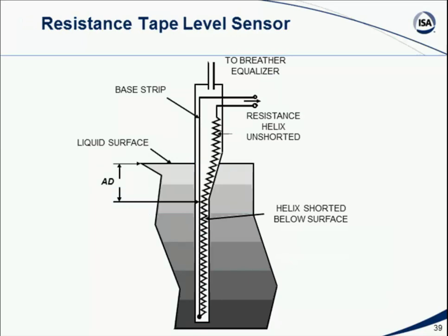Another way that we can make a measurement of level in the tank is by using a resistive tape level sensor. The best way to think about this is that I've got a long pipe made out of soft, flexible plastic that is inflated by a little bit of air pressure inside of this plastic tube, but the inflation pressure is very small, and if you were to press against it, the tube would crush down and collapse. And I've got a set of wire that runs down one side of the tube and then down the other side of the tube. And that wire has a certain resistance. And in fact, it's a helically wound resistor.